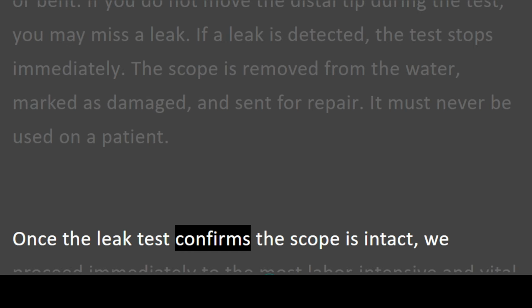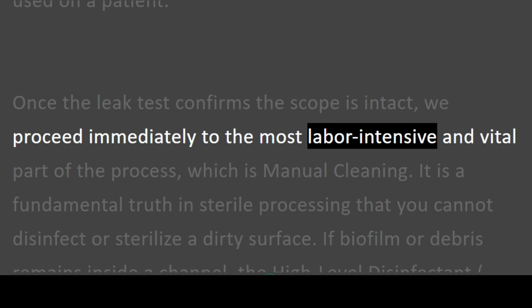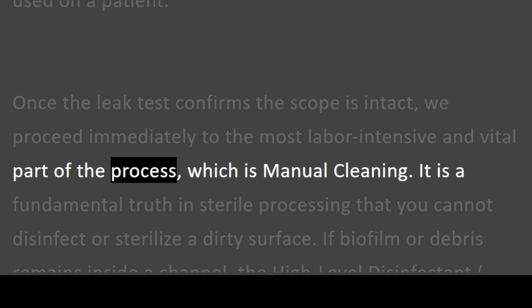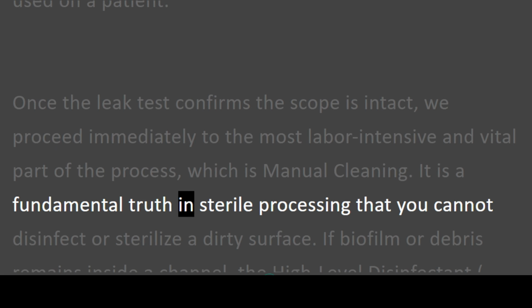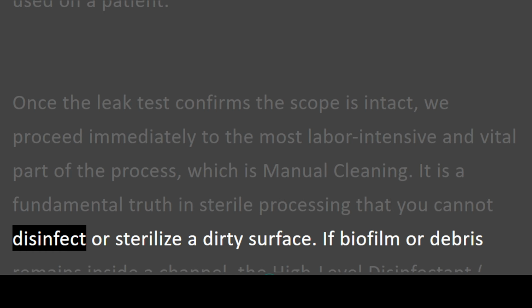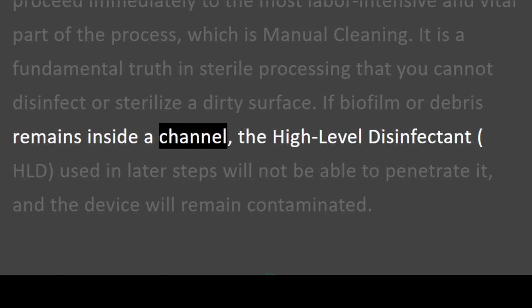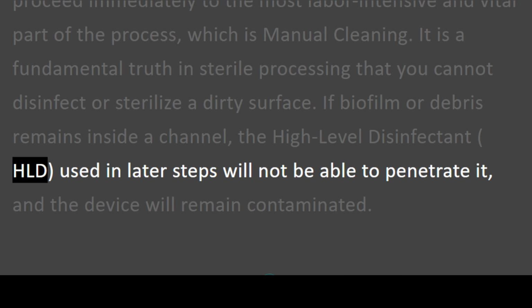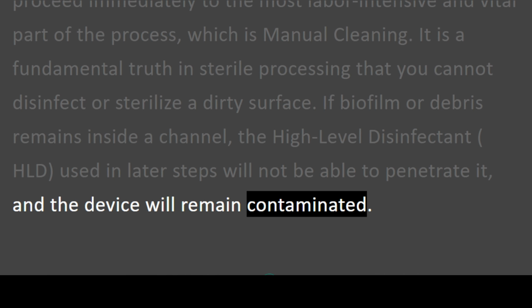Once the leak test confirms the scope is intact, we proceed immediately to the most labor-intensive and vital part of the process, which is manual cleaning. It is a fundamental truth in sterile processing that you cannot disinfect or sterilize a dirty surface. If biofilm or debris remains inside a channel, the high-level disinfectant, HLD, used in later steps will not be able to penetrate it, and the device will remain contaminated.